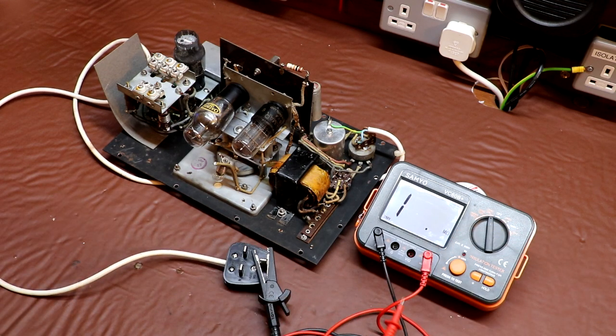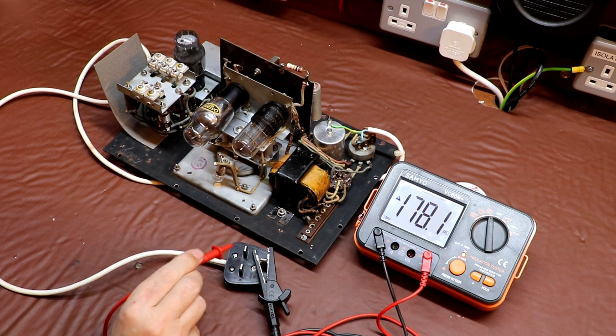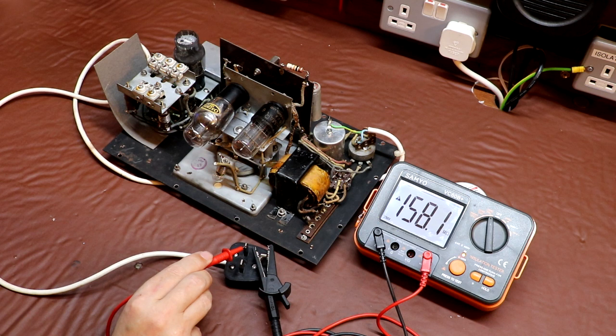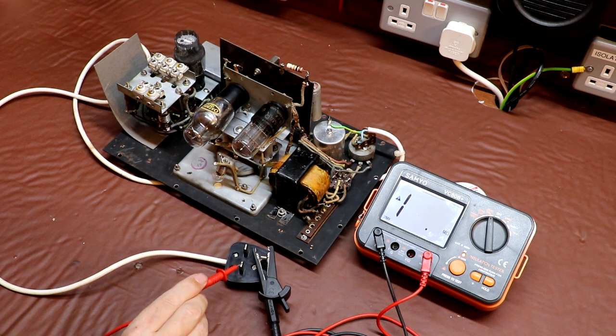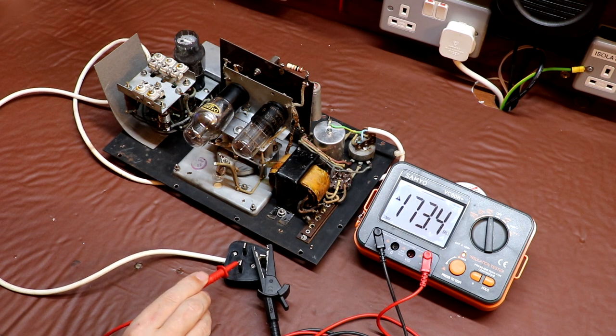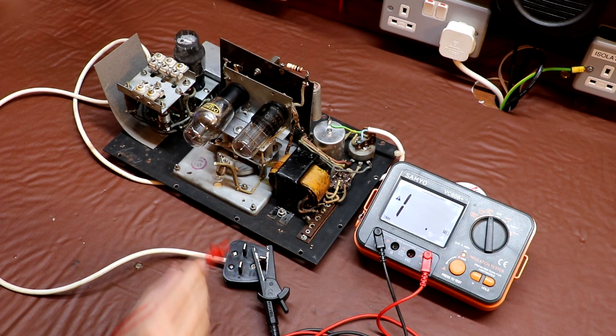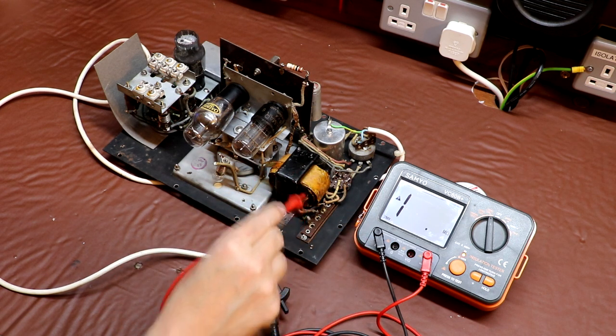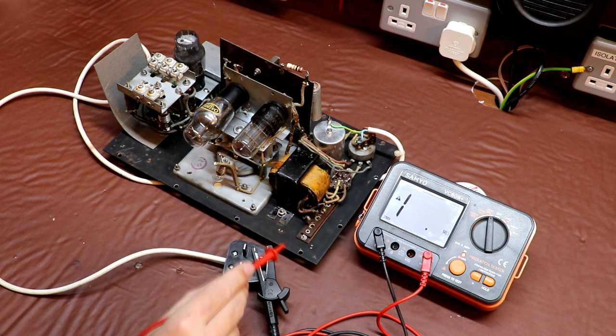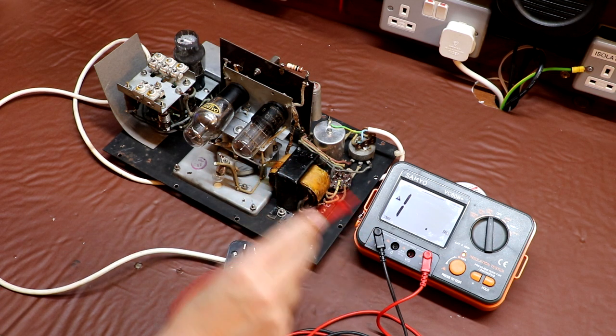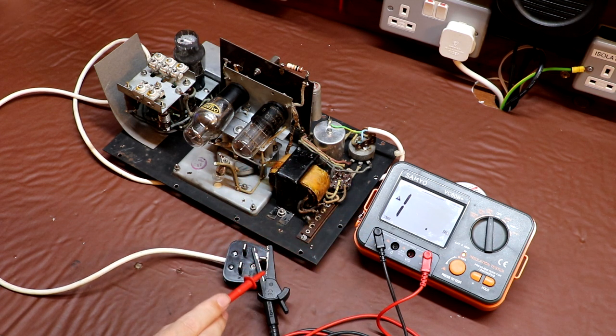The first thing that I do is make sure the meter's working, so we should get, so we're getting 0 ohms. Now I'm going to go between the live wire. We're getting 160 meg ohms and climbing. I'm going to go to the neutral wire. We've got 168, 170 meg ohms and climbing. So we've got no leakage between the live, neutral and the earth pin. So in theory, the insulation on this transformer primary looks good, and we don't have any insulation breaking down. So having done that, we can probably go ahead and apply some power.